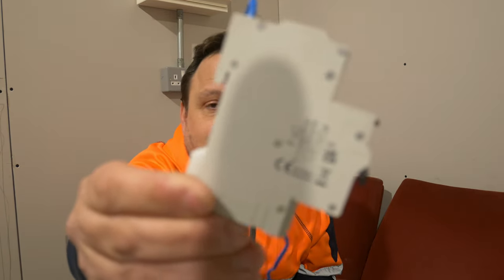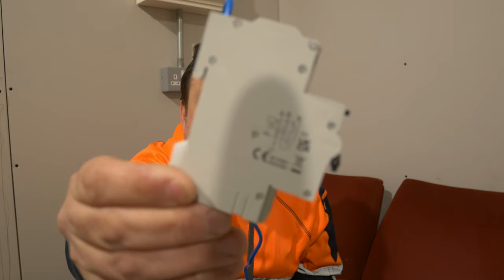You can see on the side there we've got a diagram that clearly shows the line and neutral both being opened, and there are QR codes to scan and go off and read the full data sheet on this product for those who need to. So it's still accessible to us as installers, but they are trying to cut down on a lot of the waste. You know what it's like. You get a tray full of RCBOs to install into a board. Every single one comes with a leaflet that explains what the product does. And 99 times in 100, they go in the bin.